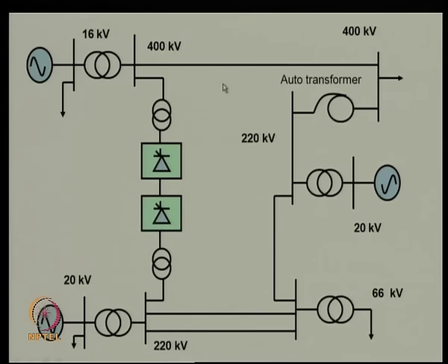interconnections called asynchronous interconnections. Now, one of the most important things of course is that loads are supplied at relatively lower voltages. They are 66 kV, which is stepped down further right down to 230 volts phase to neutral, which appears in your electricity outlet in your home. So, this is the structure of the bulk power system. From here onwards, the load is at lower voltage, and from here onwards the power system is more or less radial, but at the bulk level there is some level of meshing, that is, there are parallel paths from any node, say from A to B.